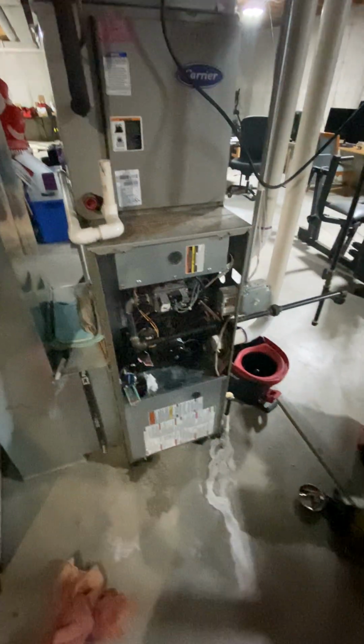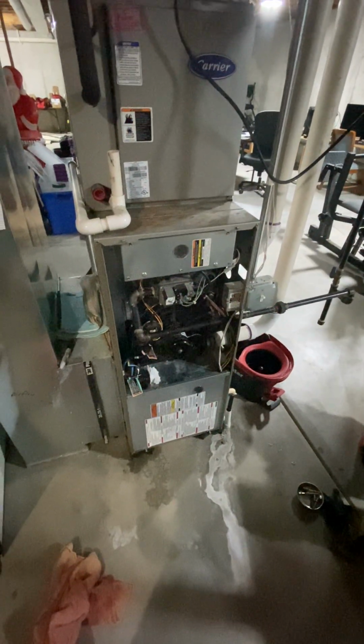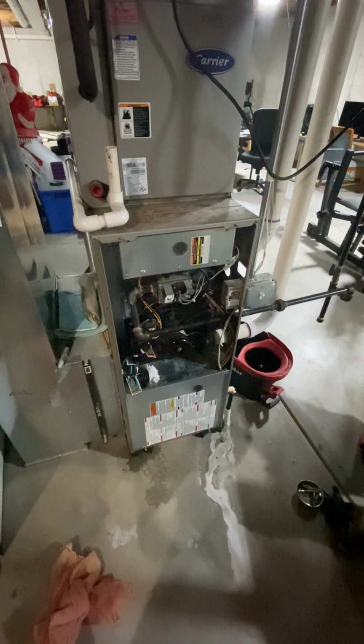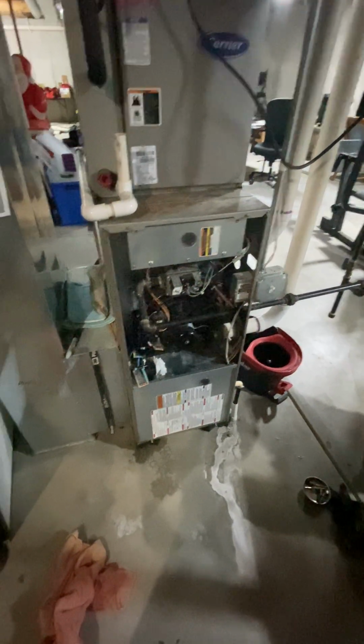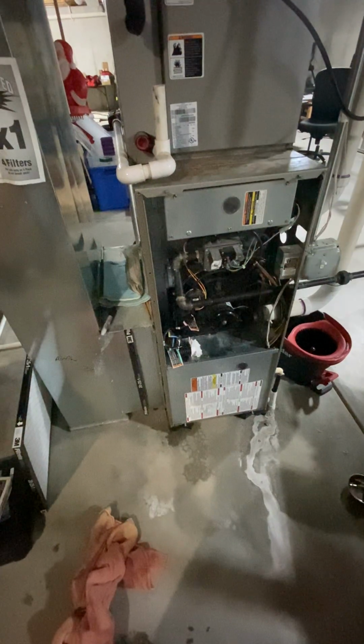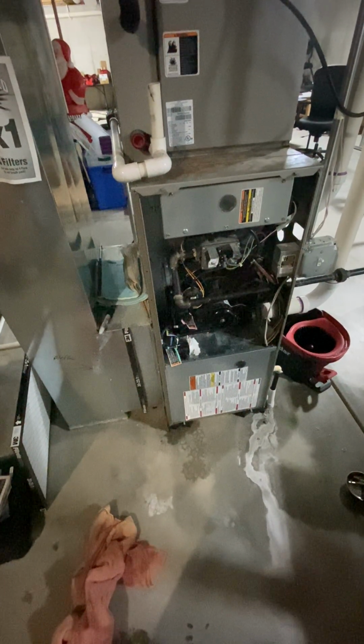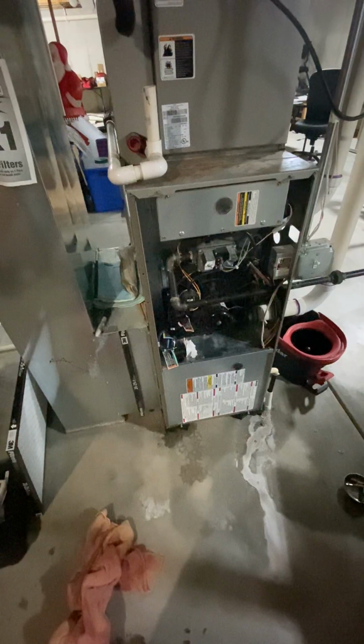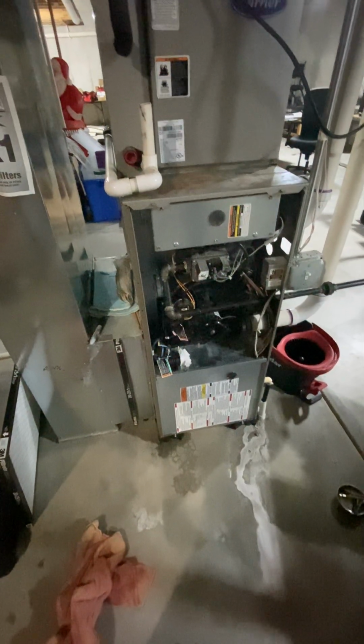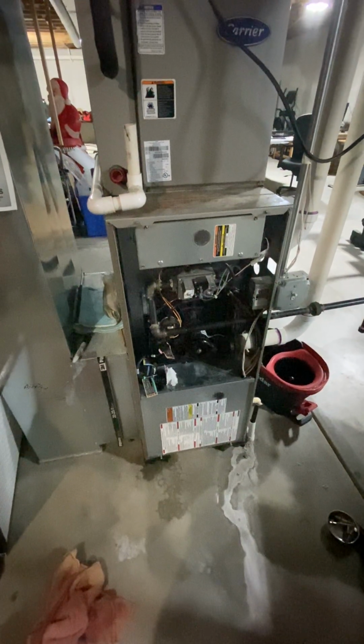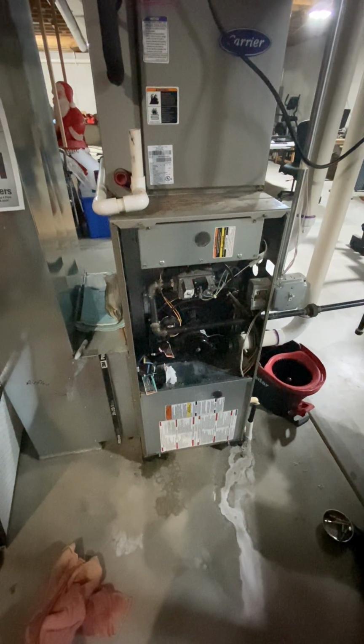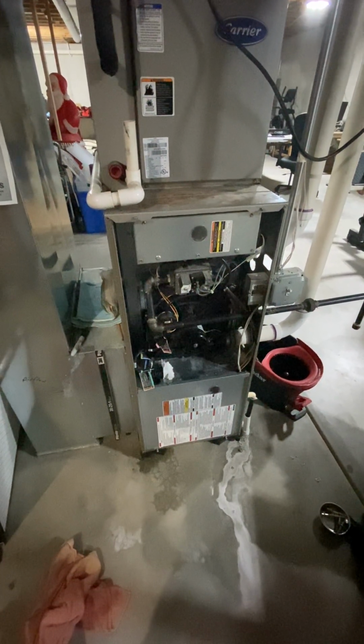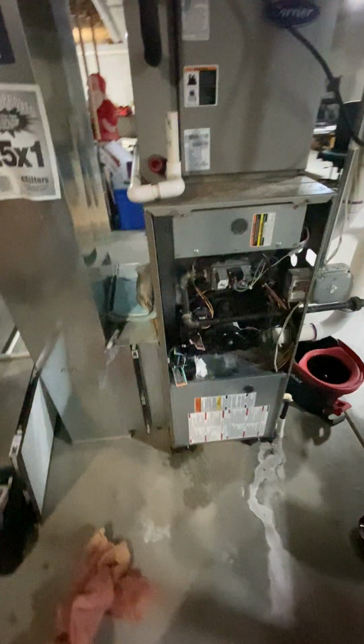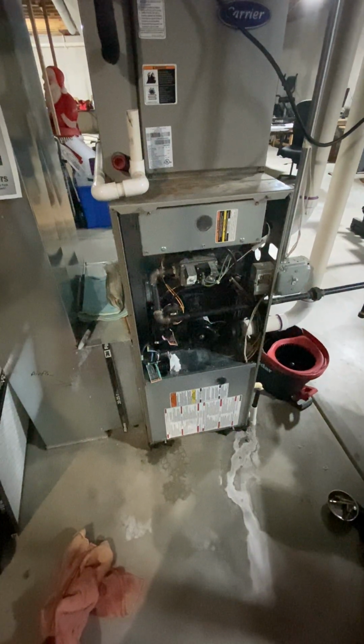Did you also want us to replace the capacitor? We also tested the capacitor. It's connected to the blower motor. It amplifies voltage to get that blower motor going. Yours is working right now, but it's way below manufacturer specifications. Eventually it will fail and then the blower motor won't come on. Even though it is working now, when you have a weak capacitor connected to a blower motor, you put more stress on that blower motor every time it starts up. So I advise to replace that capacitor as well.